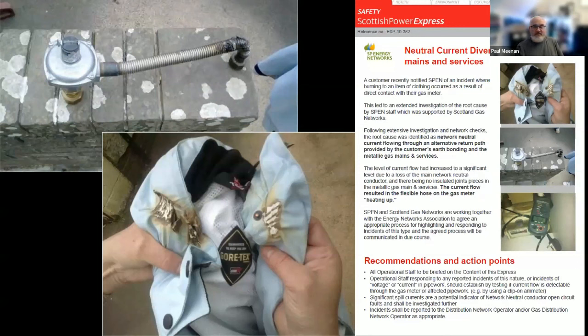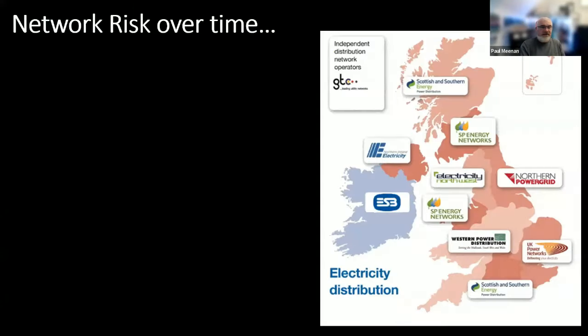One of the things that got raised to me was this health and safety report. In England, we have health and safety alerts if there is an incident. And this is an incident from a natural gas supply to a house where a coat, as you can see, fell upon the gas meter, which had something called neutral current diversion. That neutral current diversion was of sufficient level that it actually burnt the jacket. Now, this is a pipe that is benign. That shouldn't really have this, but it did. So what's going on there?